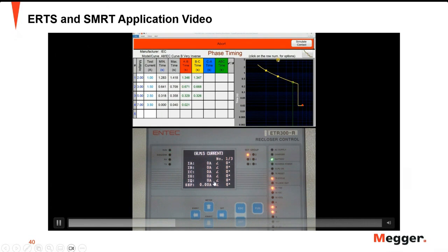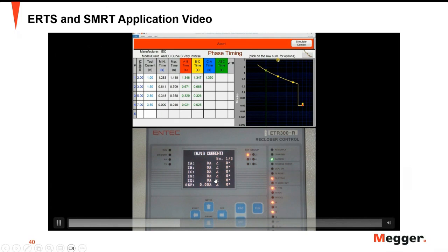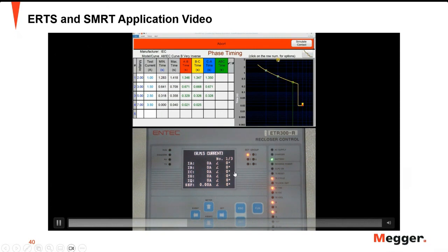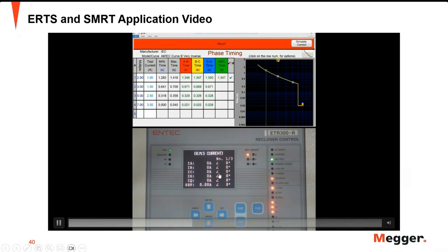If you want a record, you can also check the event logs for more detailed values of test currents. Because there is some time delay before the controller displays the measured values, it's better to get the event logs. In the event logs, you can see the magnitude of the current and what is the output — all the events required for the test can be reviewed there. It's very helpful when evaluating the results.